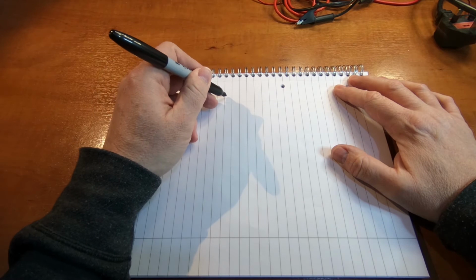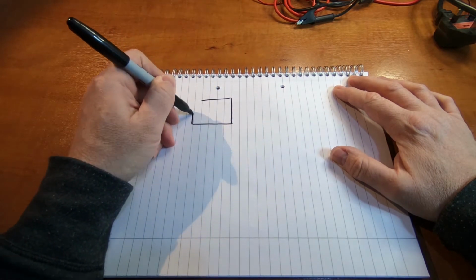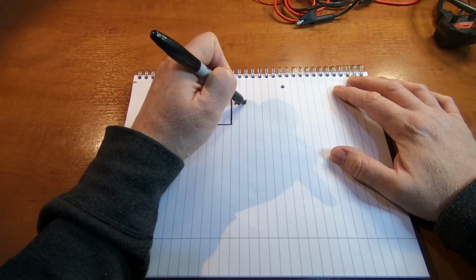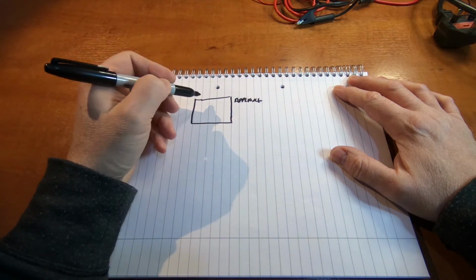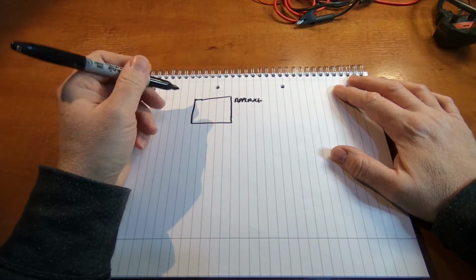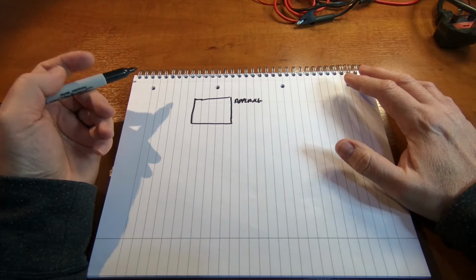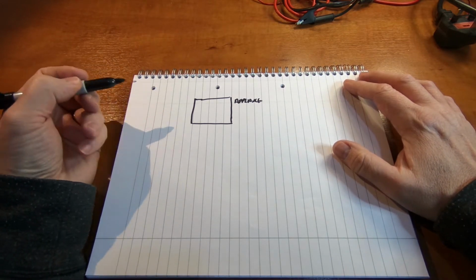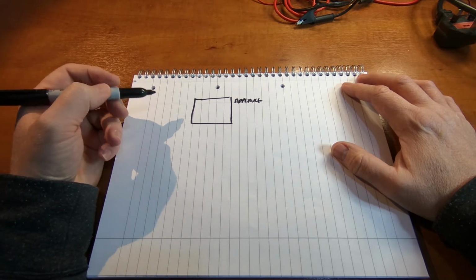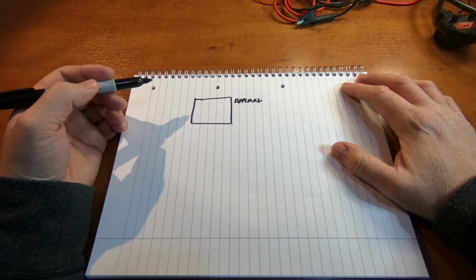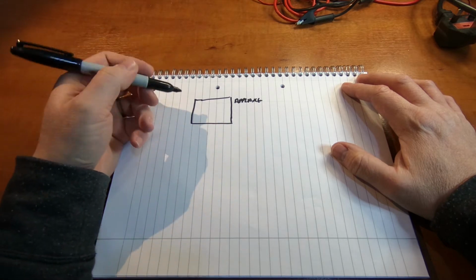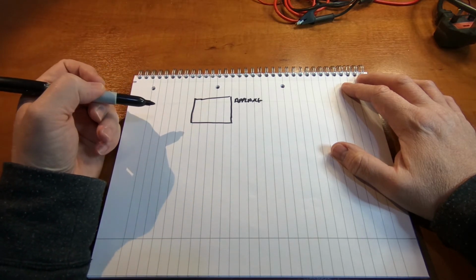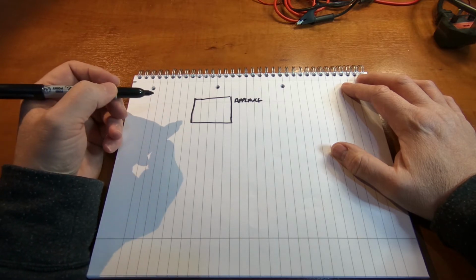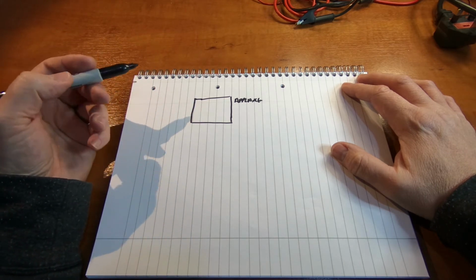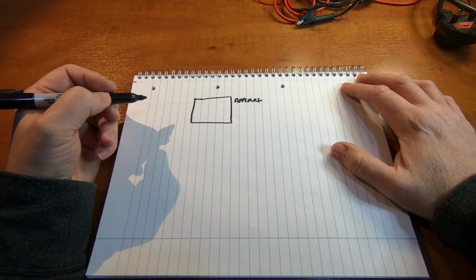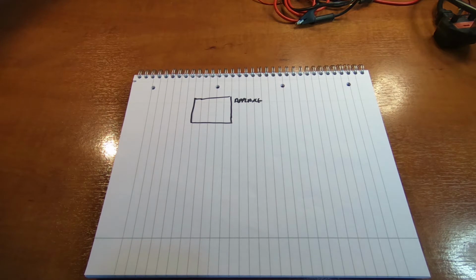So if we have a device, let's just draw a box for a device here. That's our appliance, okay. And this could be any appliance that you plug into the home. More often than not, earth leakage occurs on devices that are prone to damp or can get wet. So things like hair dryers, steam irons, kettles, especially kettles, things that have got liquid in, because what happens is the liquid in the machine can sometimes ingress into the electronics over time when it fails or the plastic becomes brittle, seals fail, and that moisture will get into the electronics, and it's that sort of wet electronics inside that's where the earth leakage can occur.